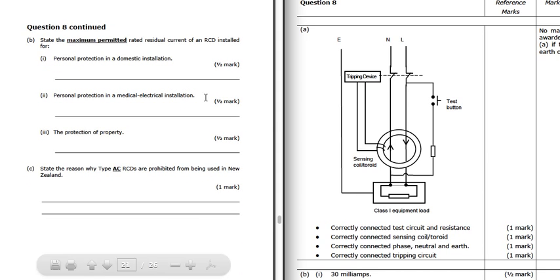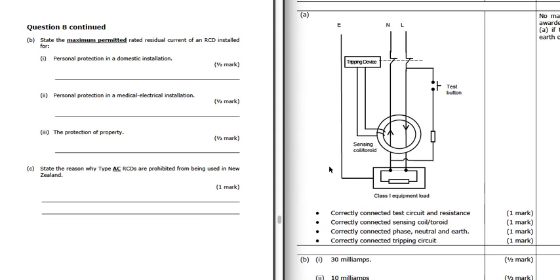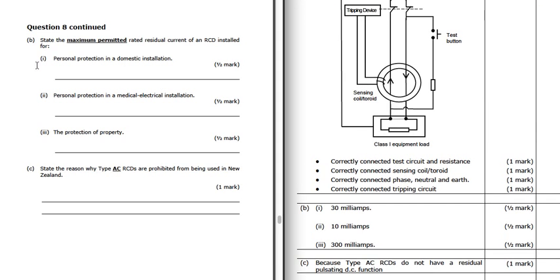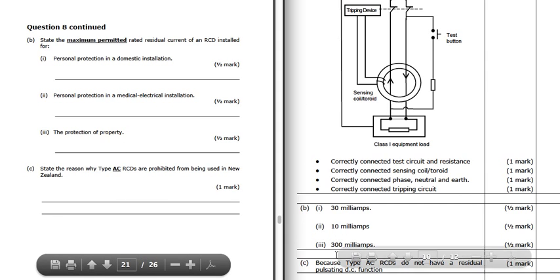State the maximum permitted rated residual current of the RCD installed. So personal protection domestic is 30 milliamps. Medical, as soon as you see medical or nursery or things like that, 10 milliamps. Property, 300 milliamps.